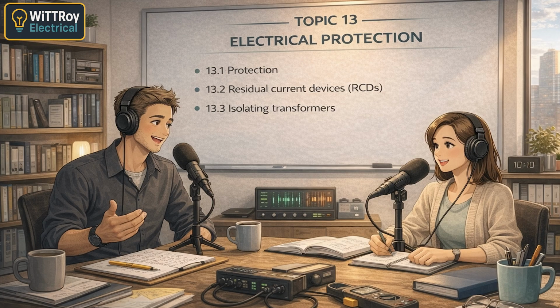Okay. Now, here's an important exam rule. How many appliances should be supplied by an isolating transformer for maximum safety? 1 appliance. Correct. Maximum safety is achieved with 1 appliance only. What if there are 2 appliances? That's where the risk increases. Because you could touch 2 metal parts. Exactly. 2 exposed conductive parts at different voltages can recreate a shock path. Even though it's isolated. Correct.